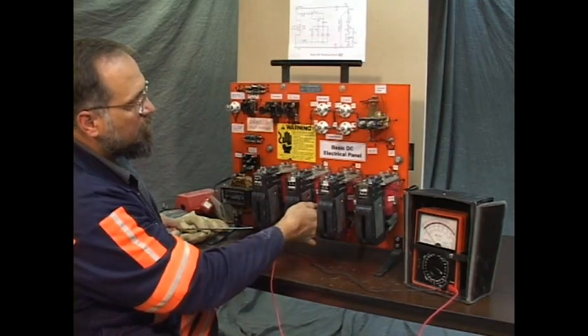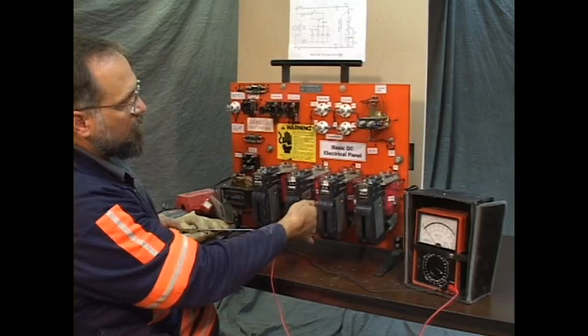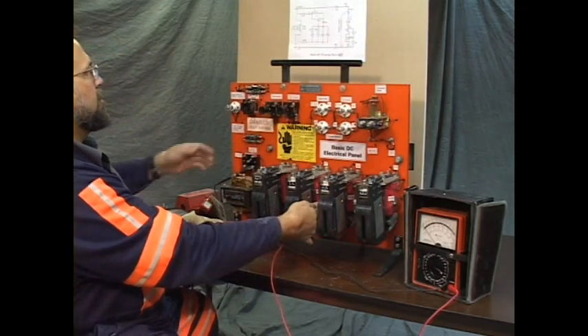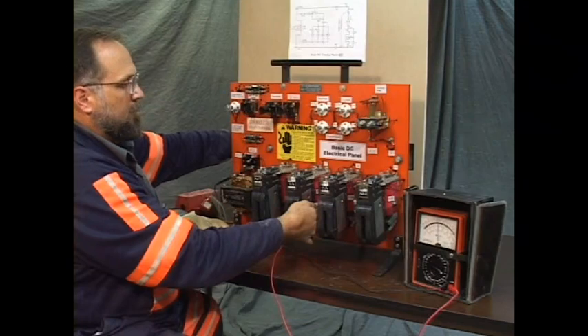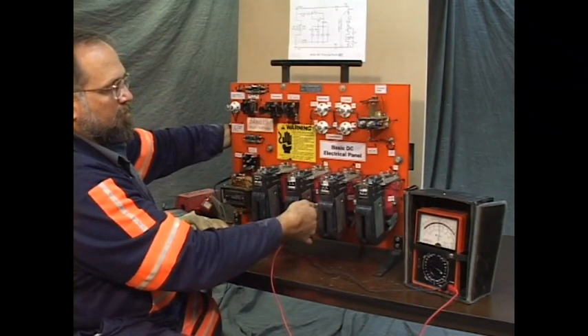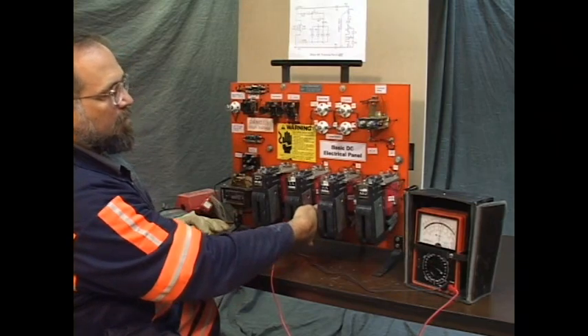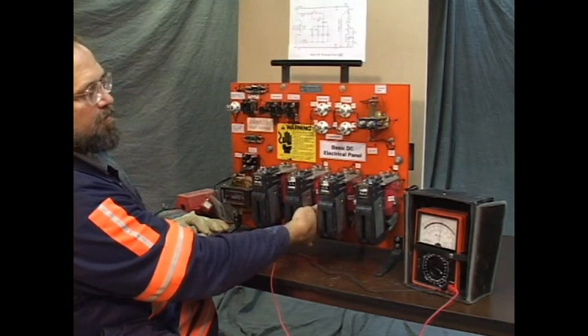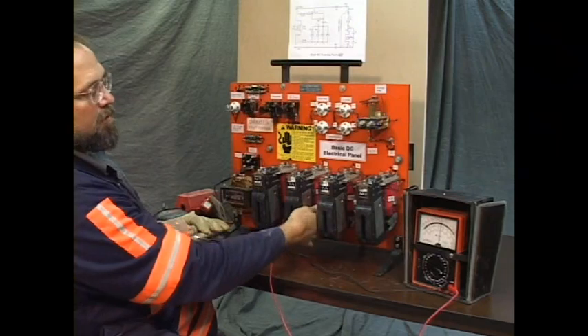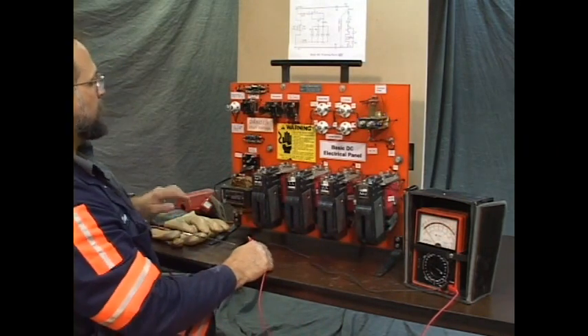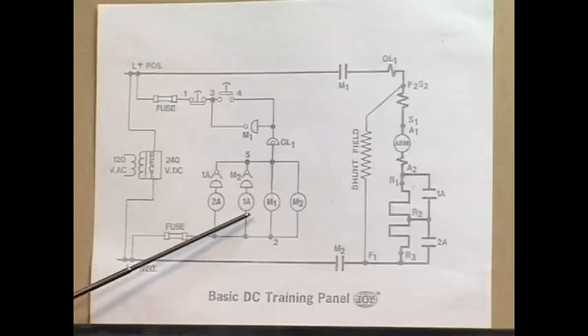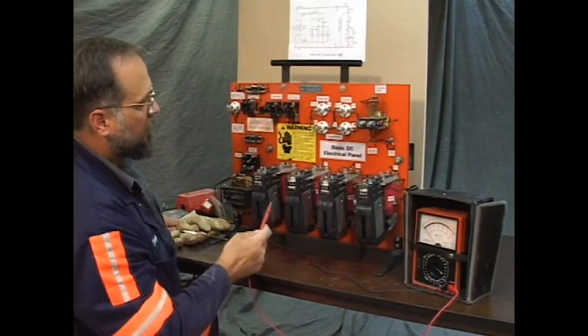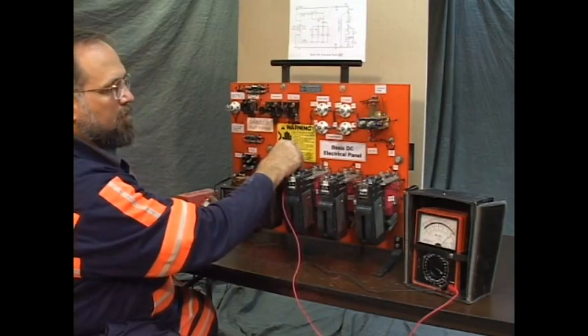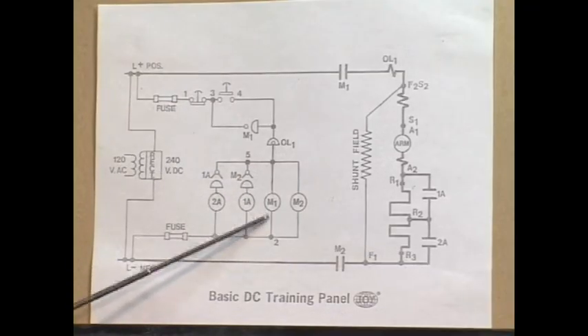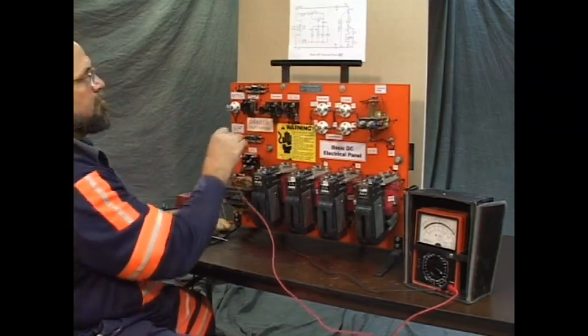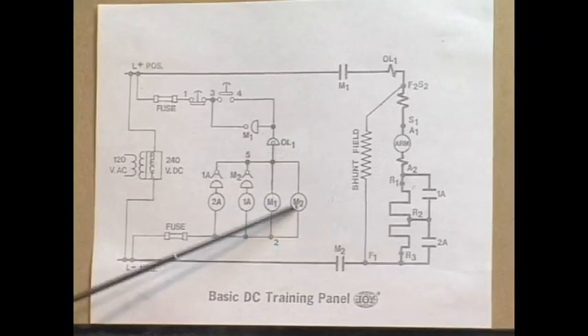Negative of the 2A coil. Well then, we've got a problem. That's one of the incomplete readings I was referring to. I believe we have a dirty switch, but you can see it did make. The next point, 1A coil, negative of 1A coil. That's good. Negative of the M1 coil. It's good. And the negative of the M2 coil.